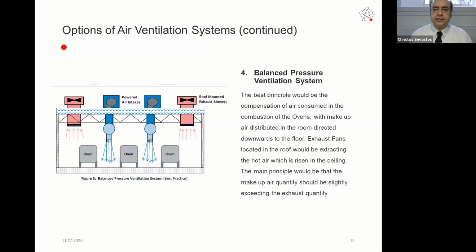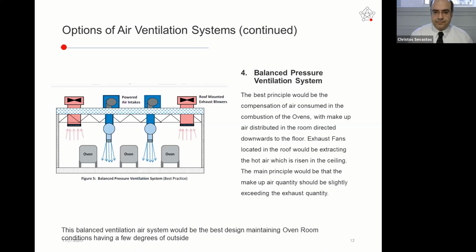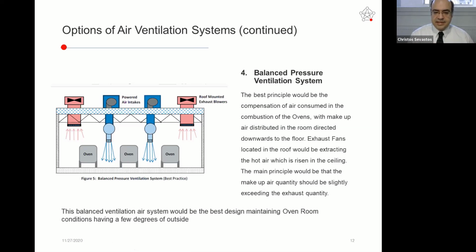And roof-mounted exhaust blowers are extracting the heat. So we are going to have air movement currents inside by blowing the proper amount of air and by extracting the air and the heat outside. The hot, humid air is extracted, cold air currents are being supplied in the lower point of the ovens. This balanced ventilation air system would be the best design, maintaining oven room conditions within a few degrees of outside.